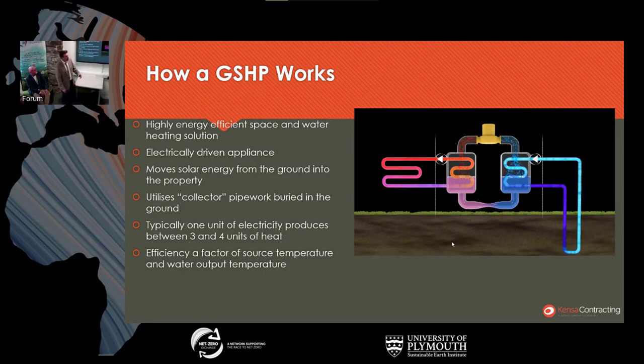When you put 5 degrees through a refrigerant fluid, it increases the temperature enough so it boils. Once the refrigerant fluid has boiled and turned into a gas, you can put it through the compressor. That's the bit that uses electricity. So the 1 kilowatt of electricity takes the 3 kilowatts from the ground, and that's how you get your 300 to 400% efficiency.